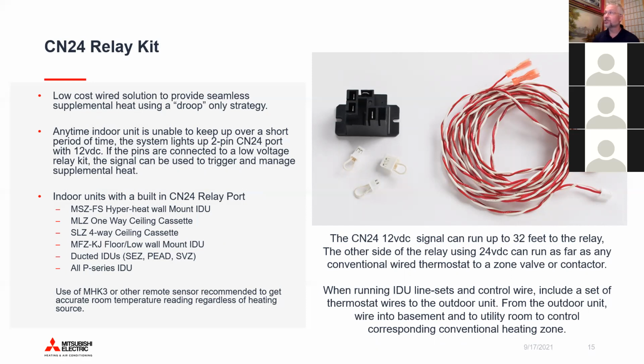The other end of the wires are just standard electrical connectors to plug into a low voltage relay that comes with the kit. Anytime there's a call for the cavalry, you're going to deliver a 12 volt DC 0.1 amp signal to that relay. It closes the contacts, and you would just run, probably in most cases, 24 volt AC through thermostat wire, bridges that gap, closes that circuit, and off you go to a zone valve or something like that. So you'd have your transformer run 24 volt AC across that relay on the back end, and then go to a zone valve or a pump or a boiler trigger, same as any thermostat.